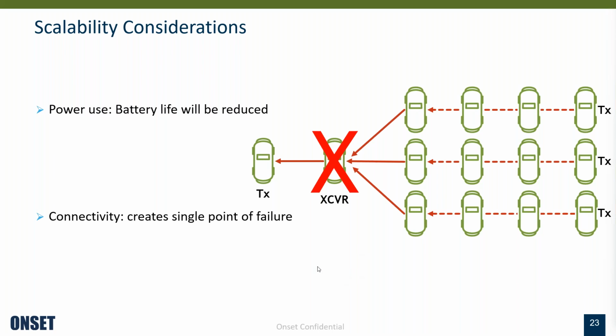With this type of topology, if you have it flat and linear, what happens is, because life happens and wireless sensor technology can be finicky, if something happens with a device that's key to transmitting data all the way back, the devices will keep logging and storing data, but that data can't make it back to the main transmitter so you can push it to the cloud and access it. So, long way of saying, just try to avoid a single point of failure where possible.